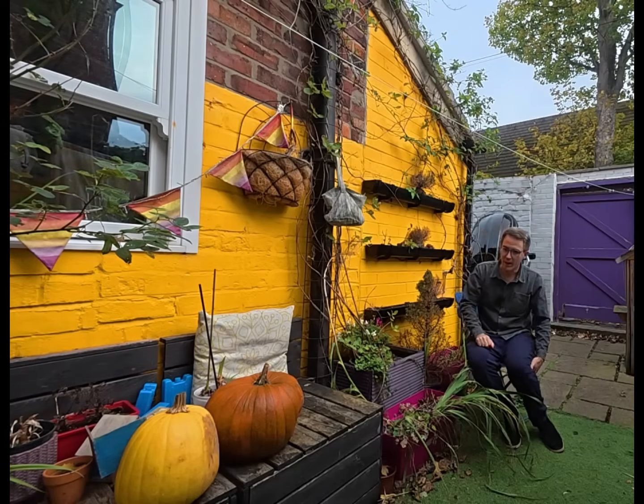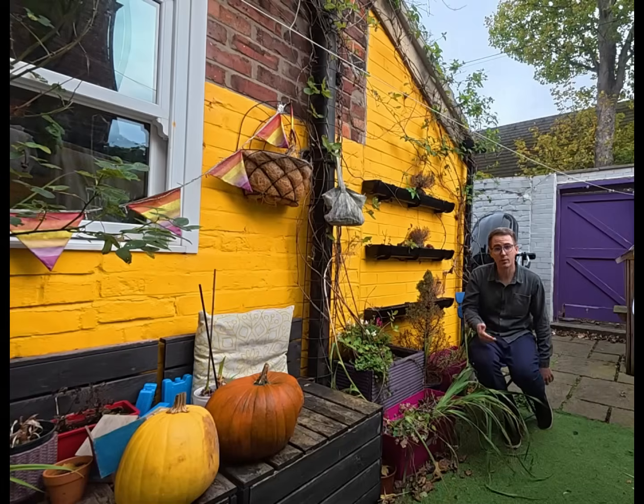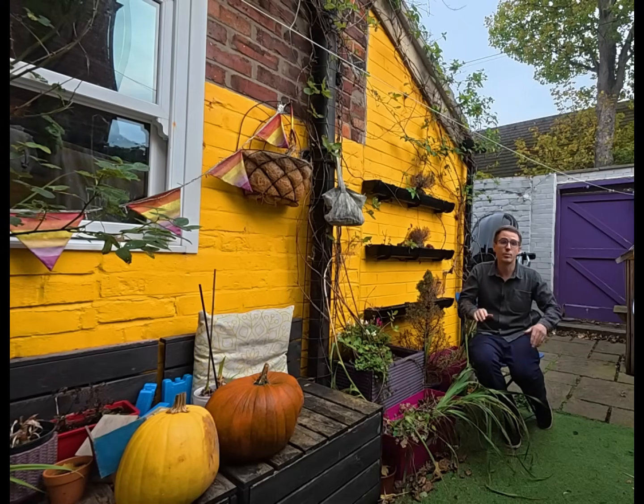I asked him if I insulated my floor and dropped off two kilowatts of heat, but he said it would only drop off one kilowatt. And if it dropped off that much we'd still need a 10 kilowatt Vaillant, which would make the same amount of noise. So that wouldn't help. British Gas are just saying no to putting a heat pump in here for noise reasons.